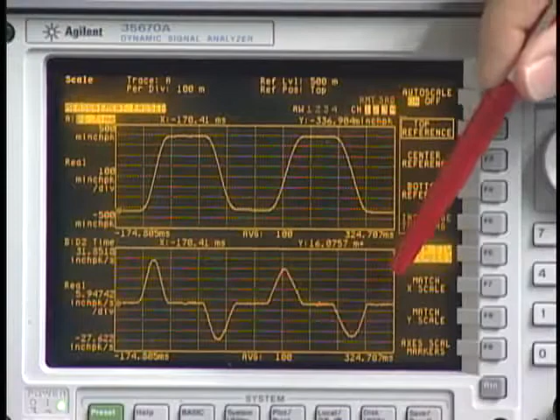That should give you some sense of what happens in a cam system when you measure the actual data. To sum up, when you look at the displacement and velocity, you see quite clean signals, partly because those signals have lower information content physically, and partly because the transducers typically used to measure them are less sensitive to high frequencies. When we move to the acceleration regime, we see a much more realistic picture of the vibration happening in the machine, which we can filter to make look pretty, but recognize that we are hiding information in this filtered signal.